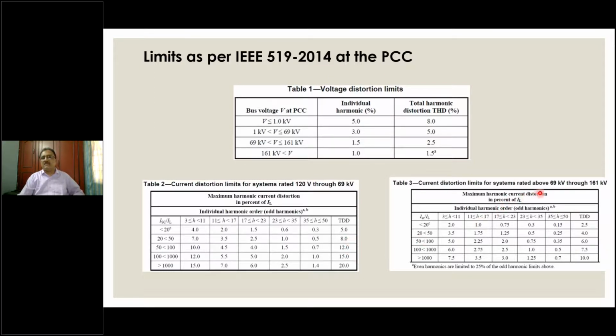This is the chart for 69 kV and above up to 161 kV. That means 110 kV industries will come here. Same slabs of ISC by IL and TDD. As you notice, the limits are mostly half of what they are at the previous level. So large industries at 110 kV will have to be very careful in understanding that IEEE 519 2014 has different charts for different voltage levels.